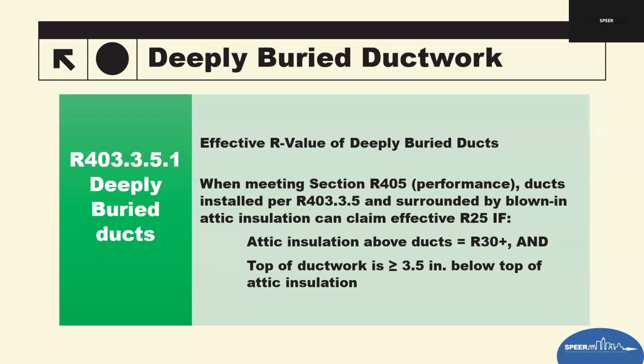And then, of course, deeply buried ducts. There are provisions for some of that. I won't spend a whole lot of time on it, but the intent here is to give designers credit for the duct systems that they're burying in enough insulation that they perform more like ducts located inside the thermal envelope. There were a lot of places where they wanted to claim the effectiveness of an R25 because of how they're blowing insulation over the ducts. So if the ducts are surrounded by blown-in attic insulation and the attic insulation above them is at least R30, the system can claim an effective duct insulation value of R25. That can help in energy modeling a lot.